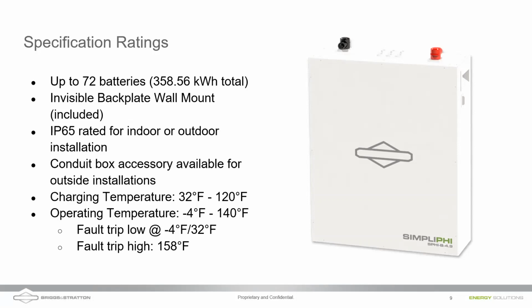We're going to talk about how to mount this guy in a second here, but there's an invisible back plate. So you're going to mount the back plate on the wall and just hang the battery on the back plate. Note that if you are installing outside, code is going to dictate that you need to hide all the wiring. And we do have a conduit box that's going to pop right on top of the battery. It's going to have knockouts for conduit as well. So if you are installing outside, you're going to want to add on that small conduit box for the exterior of the battery just to cover the wiring and allow you to easily connect conduit to hide the wiring.